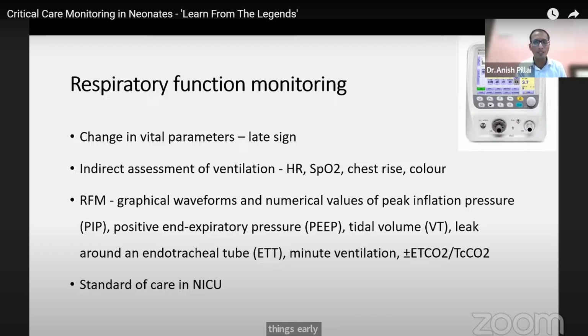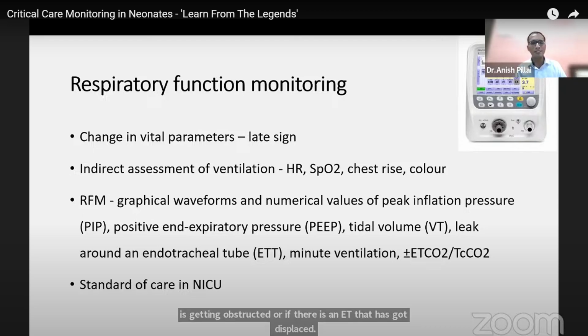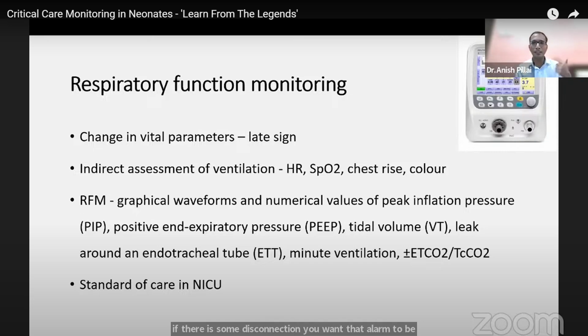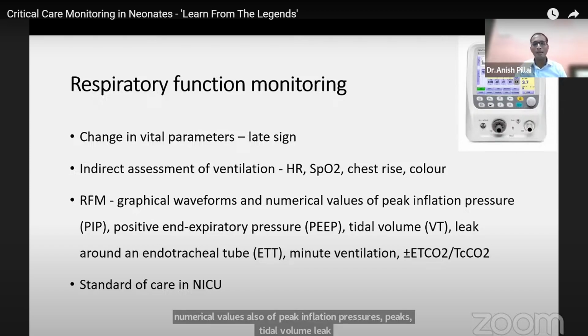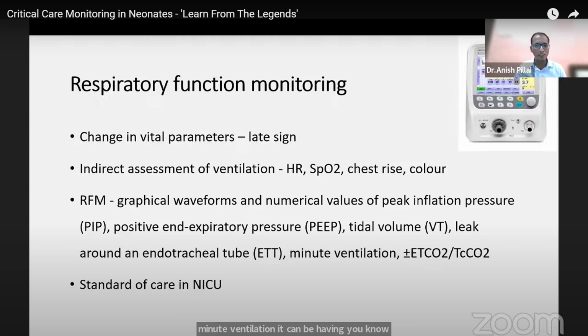If your ET tube is getting obstructed, or if there is an ET tube that has got displaced, or if there is some disconnection, you want that alarm to be faster, because the indirect assessment of ventilation that we are doing physically, which was your heart rate, SpO2, chest rise, color, will be late and you might miss it, because you are not constantly watching the baby 100% of the time. A respiratory function monitor essentially takes you back to your ventilation graphics learning. They are graphical waveforms and also numerical values of peak inflation pressures, PEEP, tidal volume, leak, and minute ventilation. It can also have an EtCO2 attached to it.